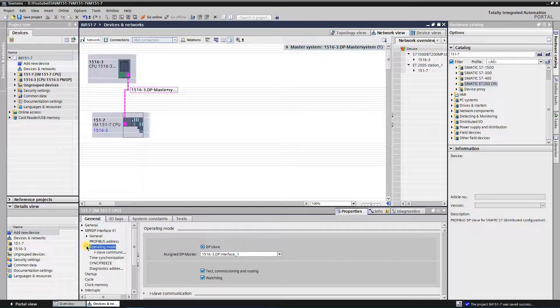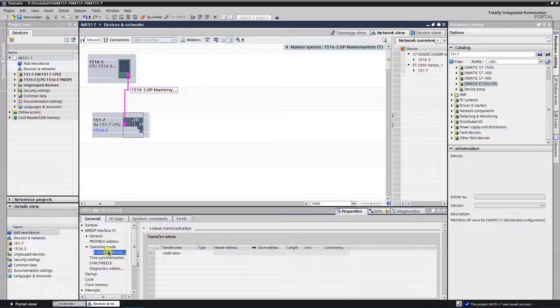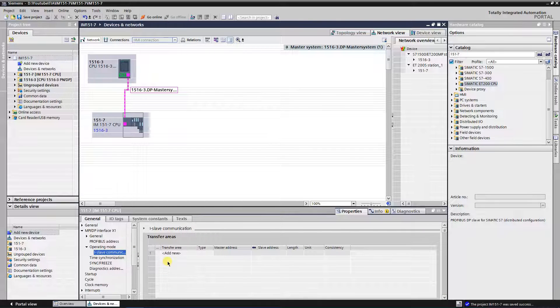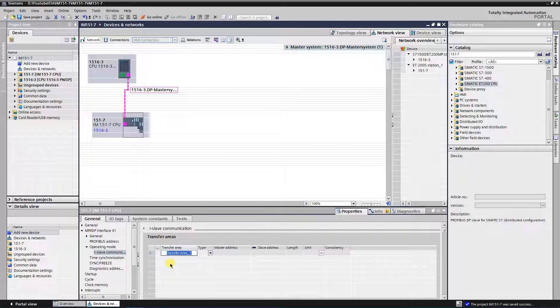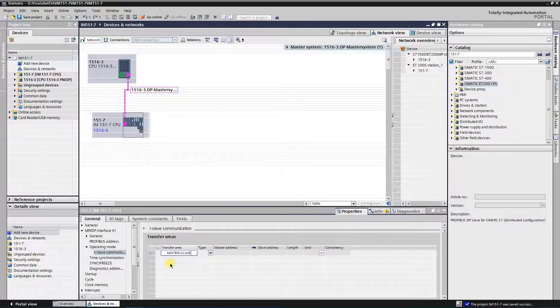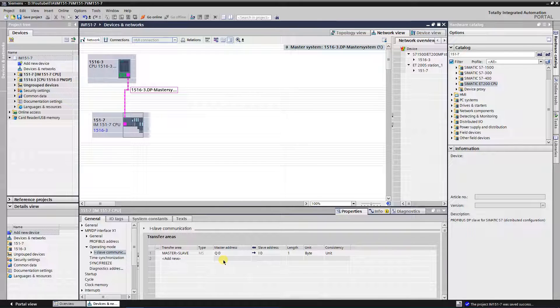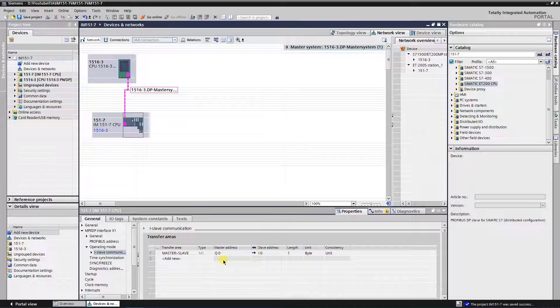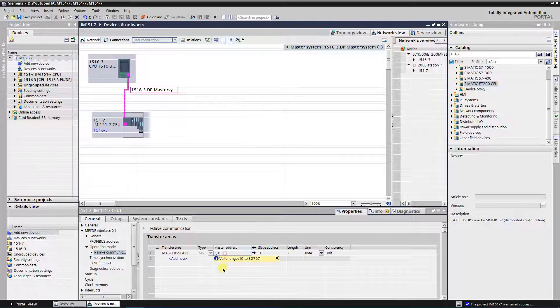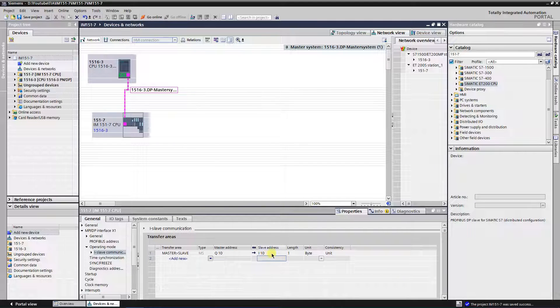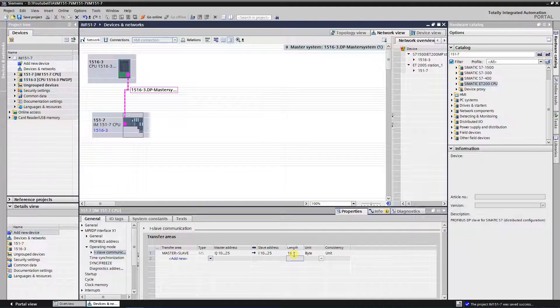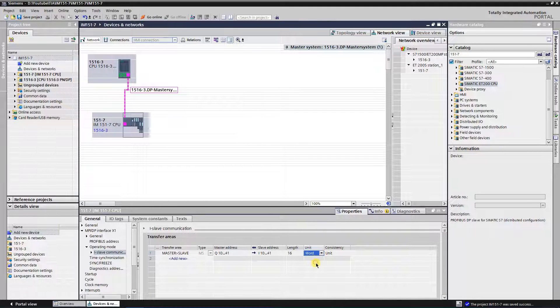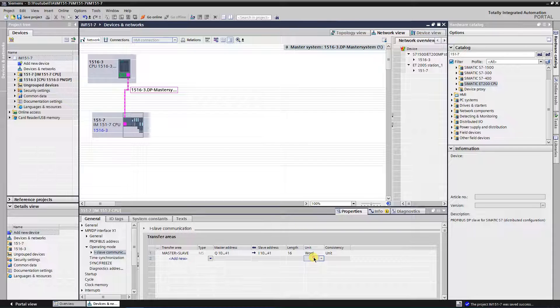Expand operating mode and select i-slave communication. In the column transfer area, click on add new. This one will be configured sent data from master to slave. I will name it according that, master to slave. To get data from master, you need to specify the range of outputs on the master side and corresponding inputs range on slave side. I will set 16 words starting on 10 on both sides. According to the setup, 16 words starting on output 10 of master PLC will be transferred to the input starting on input 10 on slave side.